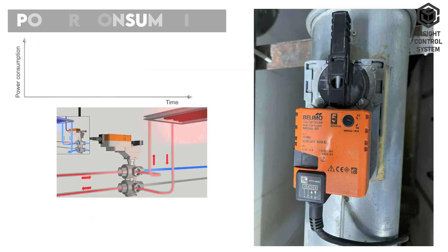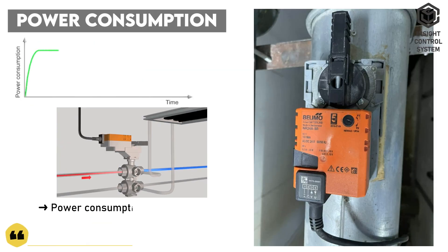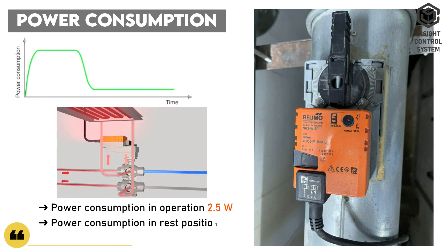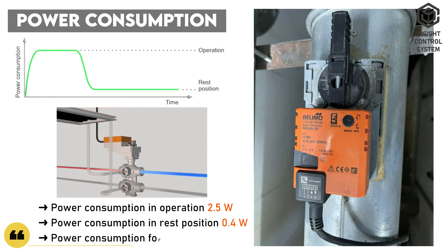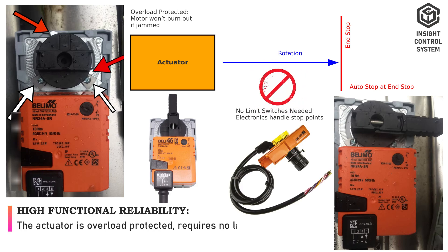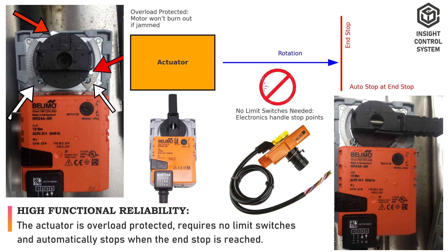Power consumption in operation is 2.5 watts; in rest position is 0.4 watts; for wire sizing is 5 VA. The actuator is overload protected, requires no limit switches, and automatically stops when the end stop is reached.